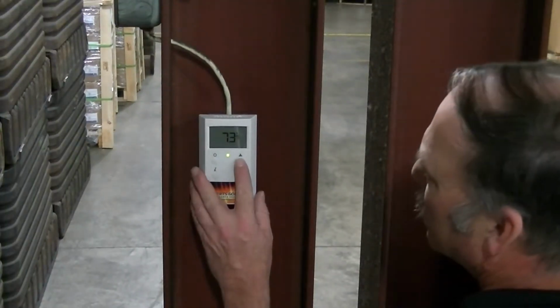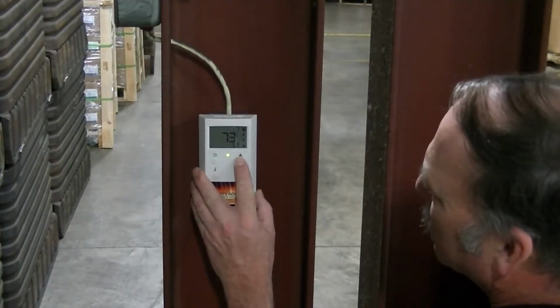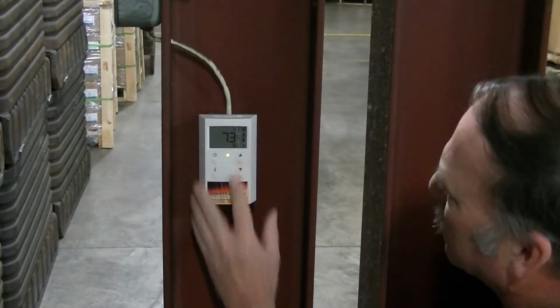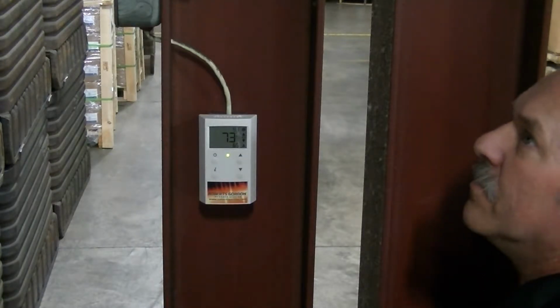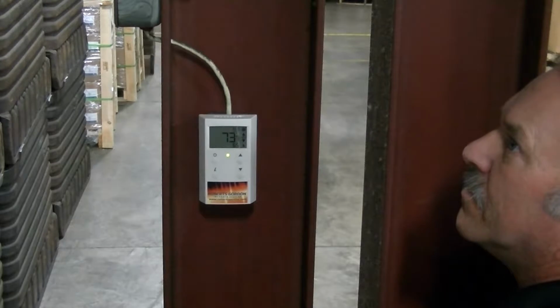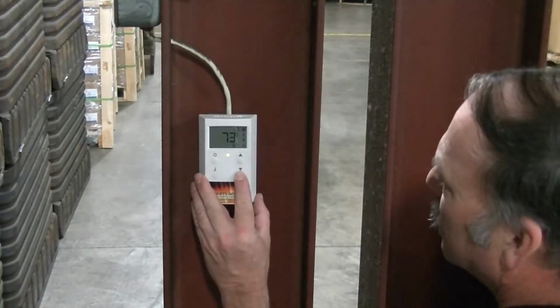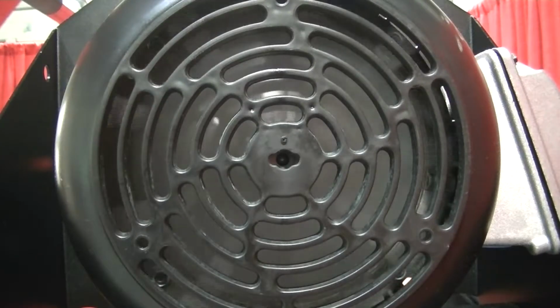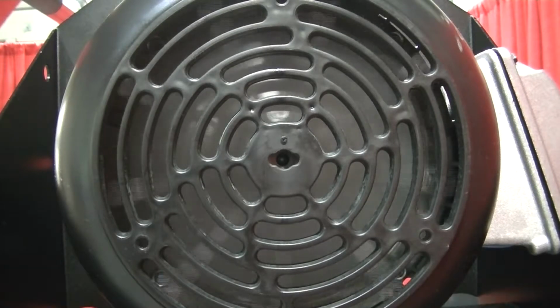Turn the zone thermostat up. Within a few seconds, the vacuum pump will start. When you hear the vacuum pump start, turn the thermostat down. When you turn the thermostat down, the pump slows down. Wait until it slows enough to see the shaft turning.